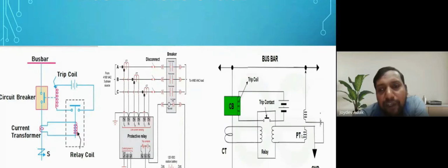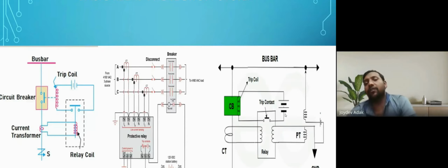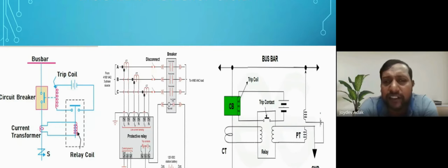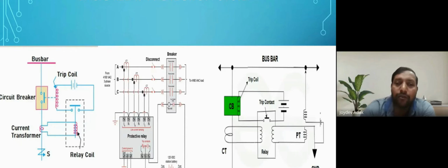If a potential transformer is used, voltage is also required for the relay for determination of the fault condition. For a distance protection relay, for any line of 220 kV or 400 kV, the current transformer and potential transformer are both required for protection purposes, because distance protection is based on the resistance or reactance method. So based on that, both are required. This is the same principle.